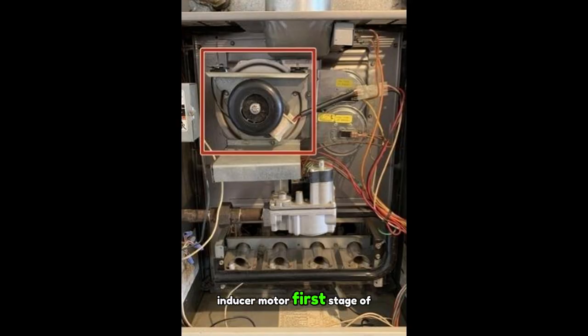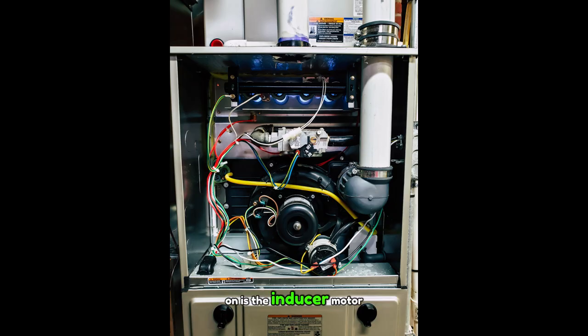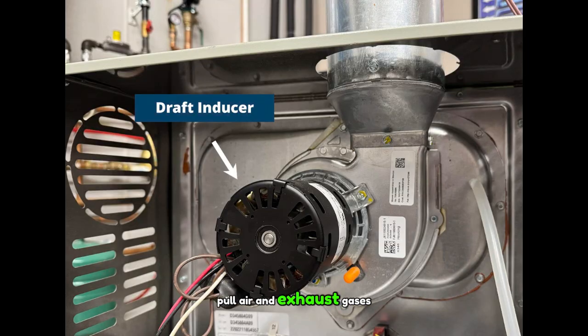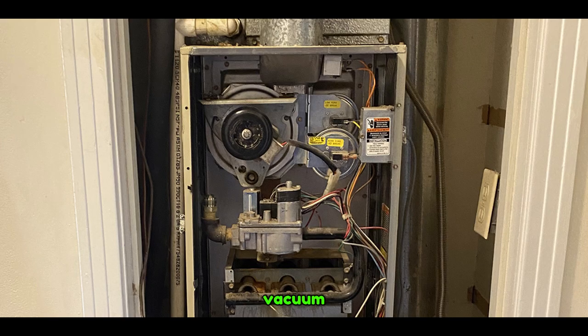Inducer motor, first stage of operation. When the thermostat calls for heat, the first thing to turn on is the inducer motor. This small motor is located near the combustion chamber, and its job is to pull air and exhaust gases through the heat exchanger, ensuring safe airflow out the flue. Think of it like a vacuum. It clears out old gases before ignition begins.